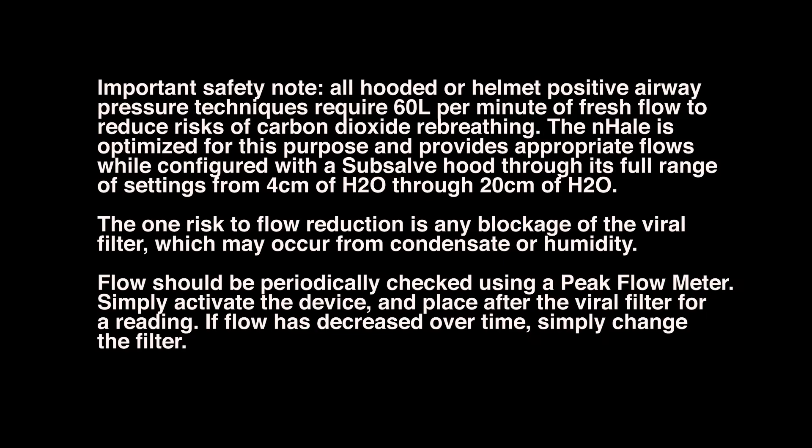Important safety note: all hooded or helmet positive airway pressure techniques require 60 liters per minute of fresh flow to reduce risks of carbon dioxide re-breathing. The nHale is optimized for this purpose and provides appropriate flows while configured with the Subsalve hood through its full range of settings, from 4 centimeters of water through to 20 centimeters of water. The one risk to flow reduction is any blockage of the viral filter, which may occur from condensate or humidity. Flow should be periodically checked using a peak flow meter; if flow is decreased over time, simply change the filter.